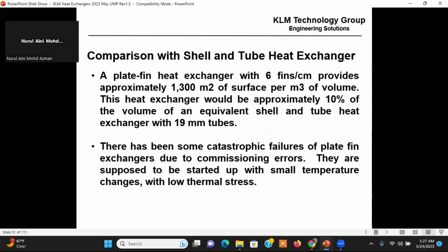So they provide a very large surface area, right? And so they're only probably 10% equivalent for a shell and tube heat exchanger. So you're going to have 90% more heat exchange. All right.